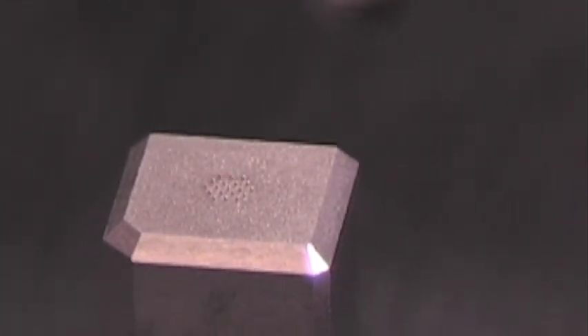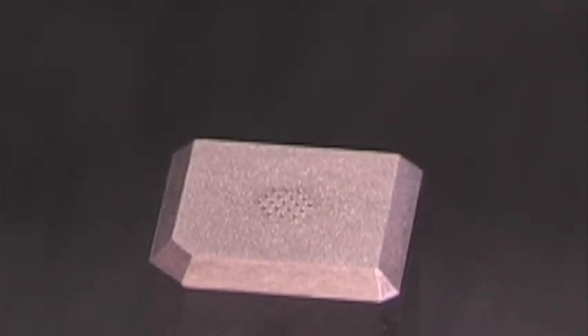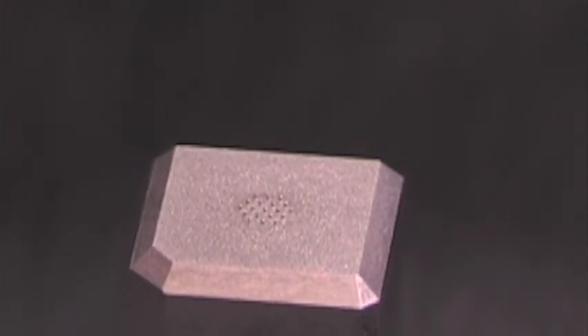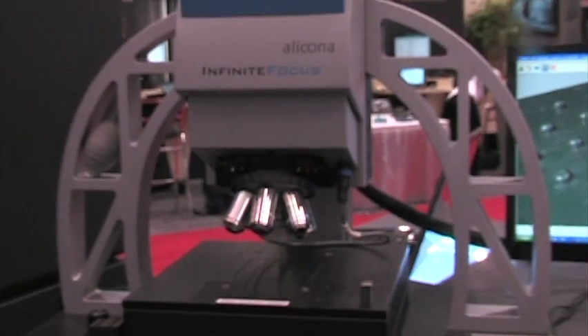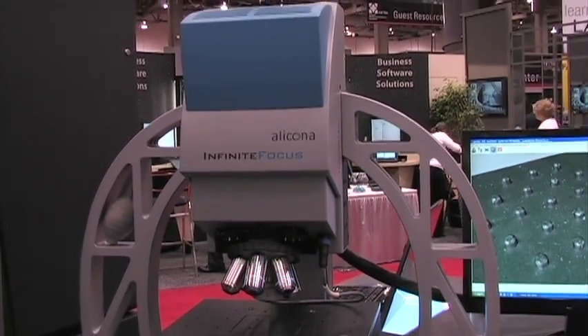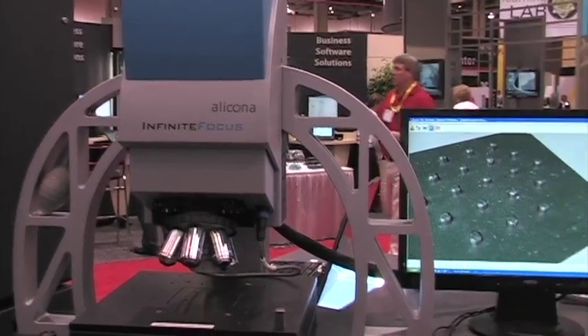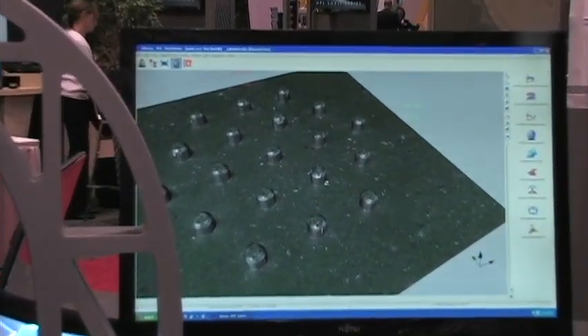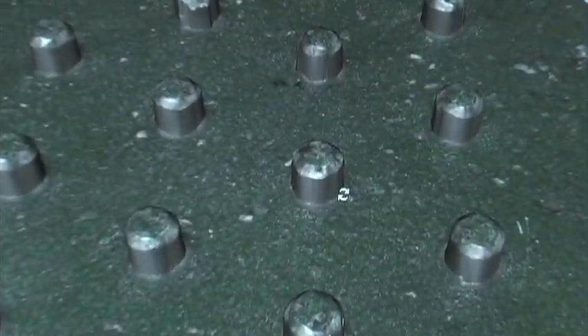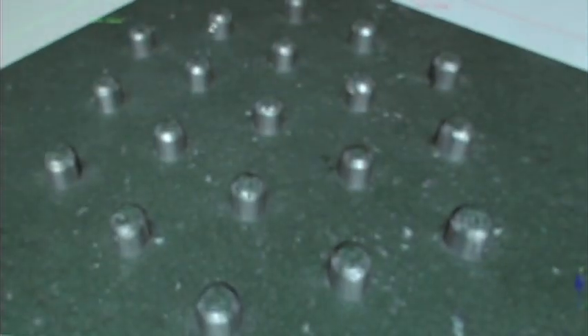For validating the machine results, we need to apply metrology technologies that allow us to confirm the machine result to levels of one micron or below. So we have a white light 3D scanning system that allows us to measure three-dimensional part surfaces. And this system has a resolution of 10 nanometers in the z-axis direction as it's scanning the part.